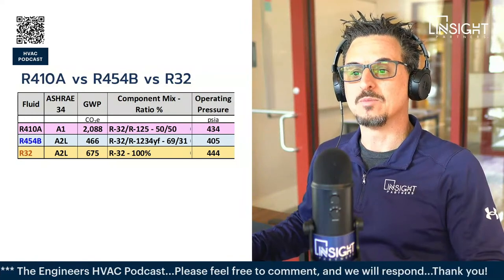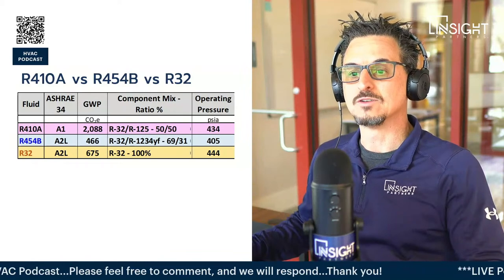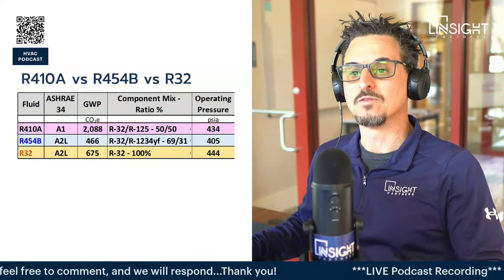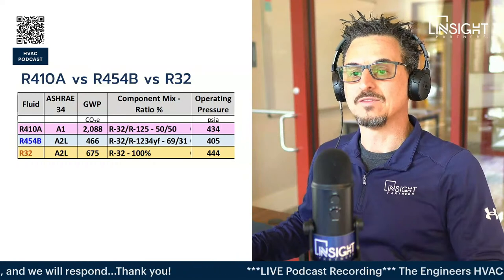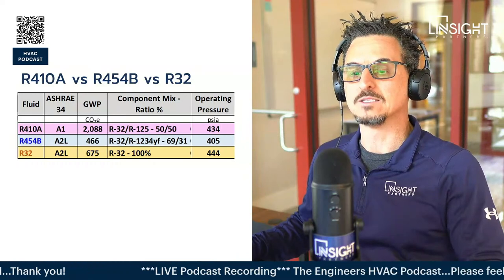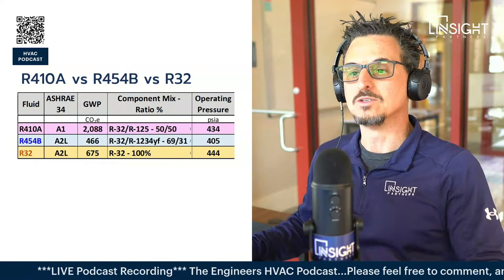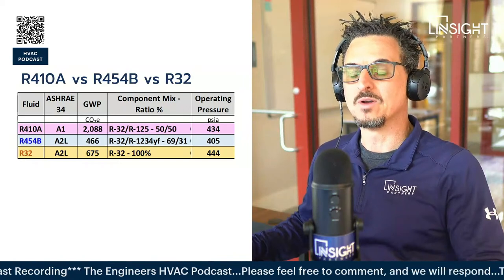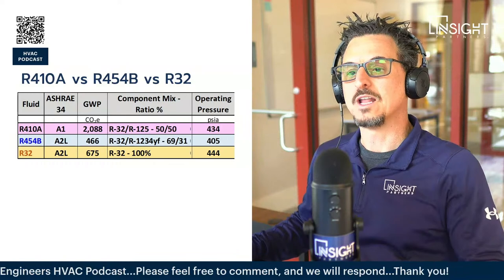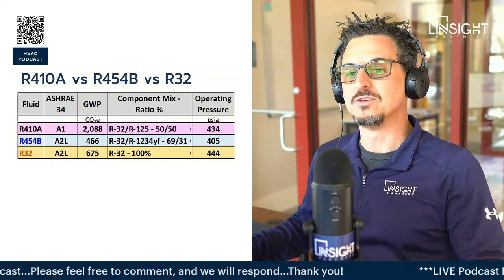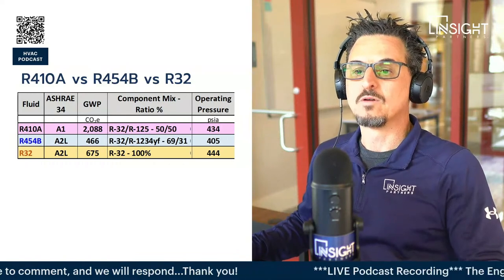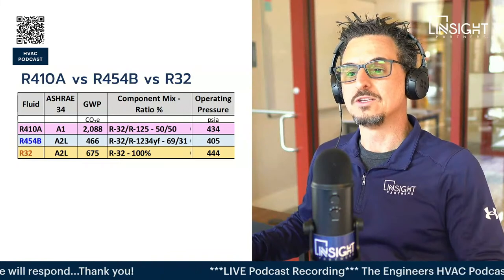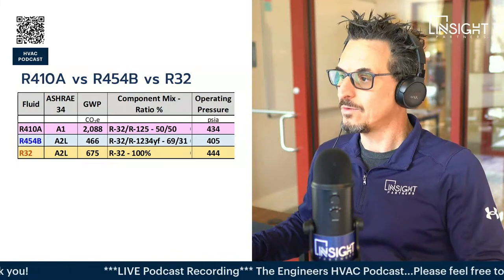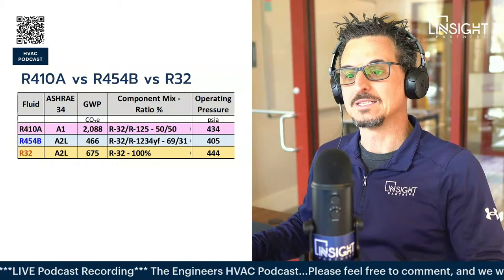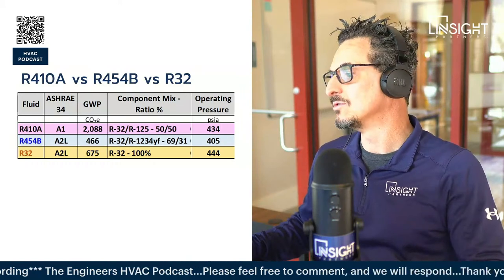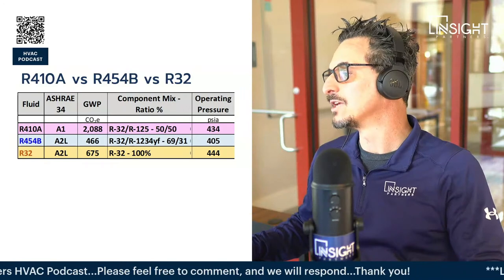You could see the GWP difference: 2,088 versus 466 for 454B, and 675 for R32. So 454B has a slightly lower GWP. The component mix, the ratio - 410A is a 50-50 split of 32 and 125. 454B is a blend of 32 and 1234yf, which I understand is an automotive refrigerant, at a 69% to 31% ratio.